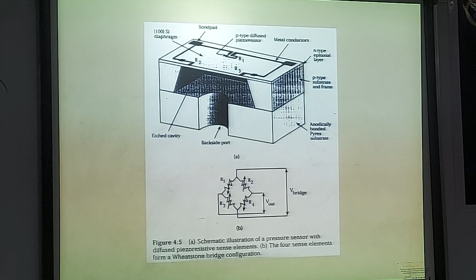Packaging is a very important step. By a suitable packaging process, we can make the pressure sensor either an absolute type, a relative type, or a differential type. If a pressure transducer measures pressure with respect to vacuum, we call it an absolute type pressure transducer. If your pressure transducer measures pressure with respect to local atmosphere, then we call it a relative type pressure transducer. Most of the biomedical pressure transducers that we see in the hospital are relative type or gauge type pressure transducers.